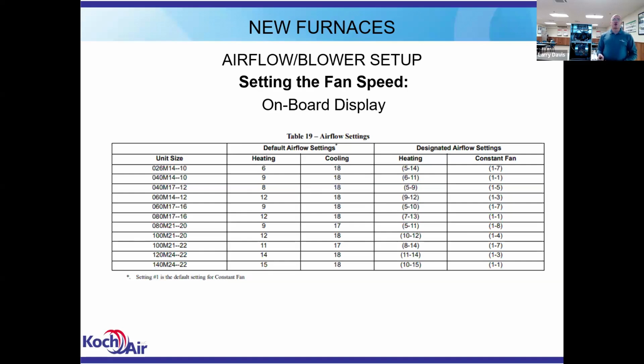And for each furnace, you'll have a range that you can set the heating fan speed and the constant fan speed. As you can see, with the constant fan speed we can't go up very high on that range. It's not going to let you set that constant fan speed any higher than that range. On the heating, those are designated. It might let you get out of that a little bit, but you just want to make sure you're maintaining your temperature rise.